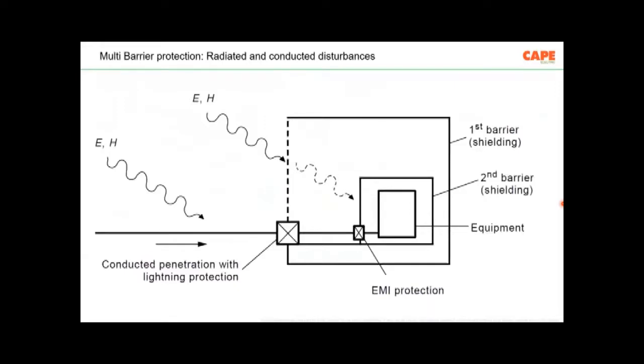So the concept which is followed for electromagnetic or EMC protection is multi-barrier protection. The protection concept is called multi-barrier protection. This is the one recommended in IEC. IEC 61000 series of standards talk about EMI, EMC. There it explains what you should do to electronics to protect them, and what you should do for an electrical system and for a building and so on. Basically, against conducted and radiated effects of various kinds of EMIs, a multi-barrier protection method is recommended in the IEC standard. Now, when we come to the electrical safety standards, such as our IS 732 or IEC 60364, the same concept which is followed for protecting electronics is also adopted, and similar things are followed everywhere.